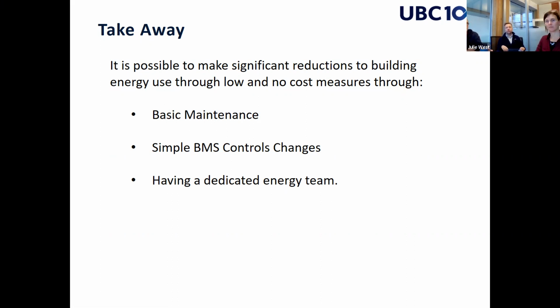And where you're looking at static reset versus air changes versus high plume exhaust, sometimes they don't necessarily get along with each other. So we're doing a deep dive into the building to see if there's further energy savings by examining the programming, looking at where things may not be what we believe them to be, and they're relying heavily on the SkySpark data and the fact that Justin did most of the energy conservation through some of the projects, except for the heat recovery chiller and the high plume. He did a lot of other energy conservation in the building, and so we're just going back, re-examining the building.